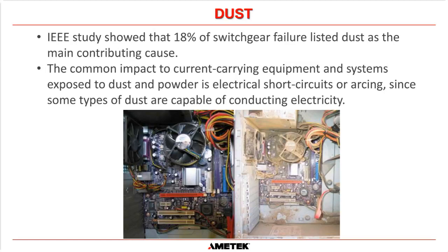So the next thing that causes most electrical failures is dust. The IEEE study showed that 18% of switchgear failures listed dust as the main contributing cause. The common impact to current-carrying equipment and systems exposed to dust and powder is electrical short circuits or arcing. Basically, the dust becomes conductive, whether the dust is conductive itself or when there's moisture or some kind of corrosive component in the air. They act together and allow tracks on a circuit board or something else to create a short circuit. And obviously that is not a good situation.